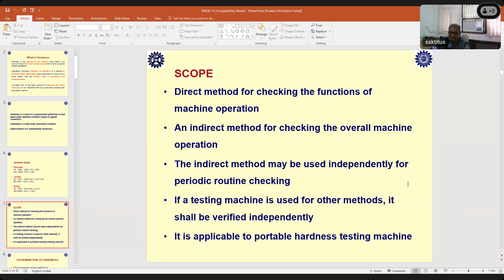And if a testing machine is used for other methods, it shall be verified independently. Sometimes hardness machines can be used for other purposes also. So we have to be very careful that the indenter's geometry is not deformed by the other methods. Every time, we need to check independently whether the machine is performing well or not. Then only can we be sure of what we are measuring using that particular instrument. This is also applicable to all portable hardness testing. There are several portable hardness testing machines available now, and the same conditions apply to them also.